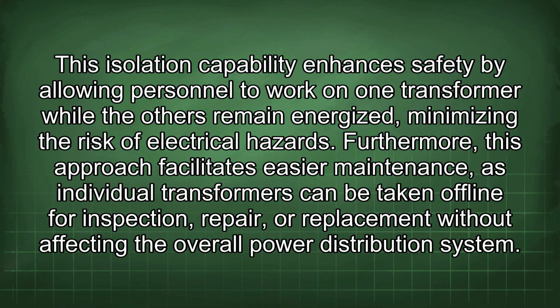This isolation capability enhances safety by allowing personnel to work on one transformer while the others remain energized, minimizing the risk of electrical hazards. Furthermore, this approach facilitates easier maintenance, as individual transformers can be taken offline for inspection, repair, or replacement without affecting the overall power distribution system.